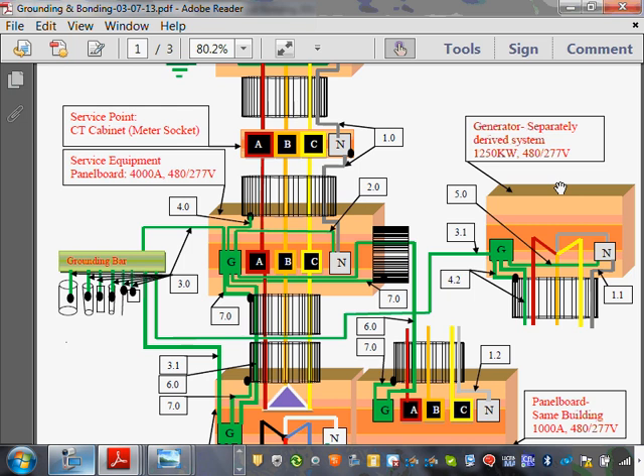In the transformer, we did not have any option, did we? We can't bond the neutral of the two together, right? Except at the panel. On the generator, you do have an option. So you can run this generator as a separately derived system by isolating the neutral. Then if you have an auto transfer switch, you have to have a 4-pole auto transfer switch, 3 for the 3 phases and 1 for the neutral, flipping them. Or you can run it as a non-separately derived system, and then you have a 3-pole auto transfer switch, and you're only switching phase A, B, and C, or hot 1 and hot 2 if you're doing single phase. Either way, the grounding and bonding are the same, with some exceptions.